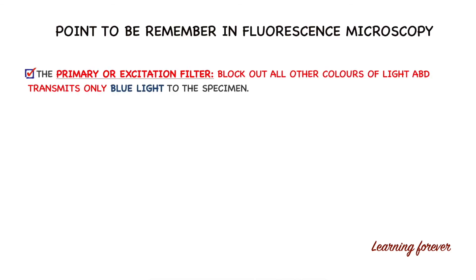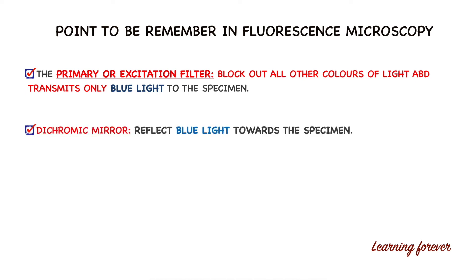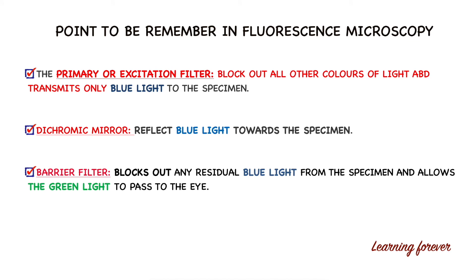Key points to remember in fluorescence microscopy: First, the primary or excitation filter blocks out all other colors of light and transmits only blue light to the specimen. Second, the dichromic mirror reflects blue light towards the specimen. Third, the barrier filter, also called the emission filter, blocks any residual blue light coming from the specimen and allows only green light to pass to the eye. The barrier or emission filter is generally selected based on the dye you are using.